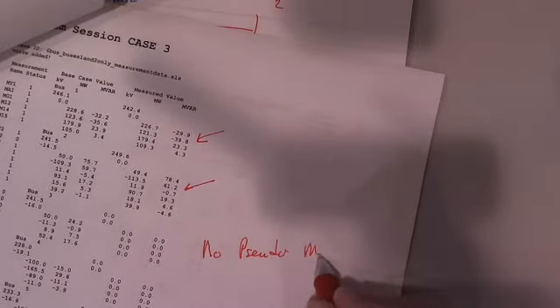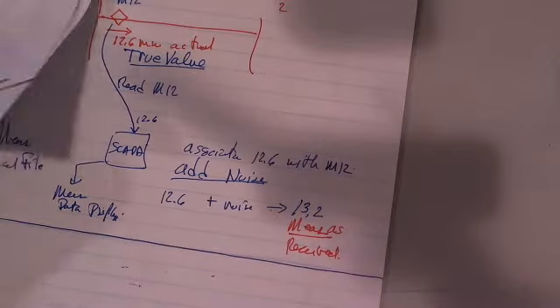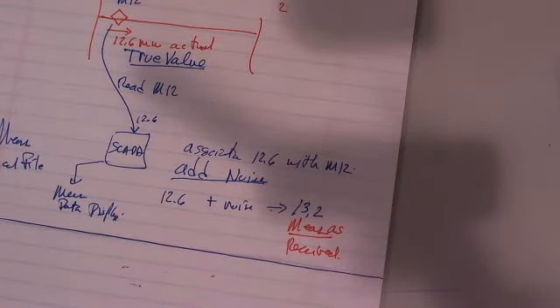Case 3, run the power flow again. Noise added, and in this case, what am I doing? I've got measures at bus 1 and 2, so there are no pseudo measurements. Nothing down here. So when I solve, once again, the TJ that it's shooting for is 16, and it gets to be 12.4. So it meets our test on the first try, and says there are no bad measurements. So that's just to show you there are no pseudo measurements in that case. And I've got a couple more cases to show you here.